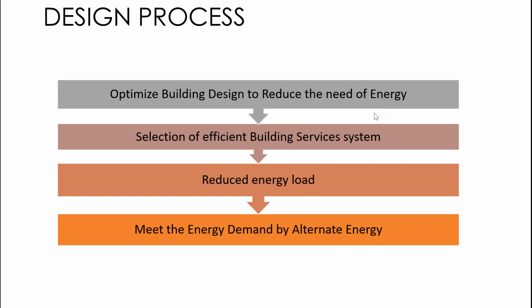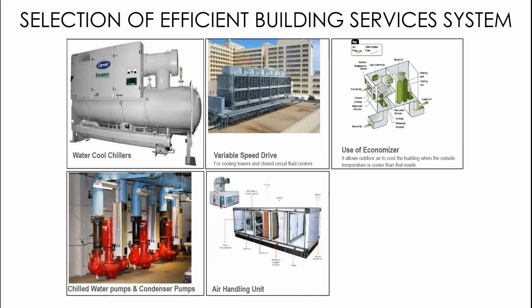If I talk about building air conditioning, the entire system is a water cooled central plant. We have water cooled chillers placed in the basement, and these chillers work with cooling towers which are provided with variable speed drives. These cooling towers are not on the building terrace but at the site level, which has helped me reduce my pumping from the chiller to the cooling tower. So I need not pump it all the way up to the terrace, I just need to pump it to the site level. Now this is primarily the high side part.